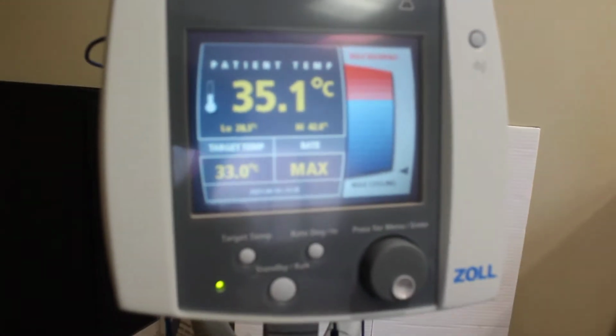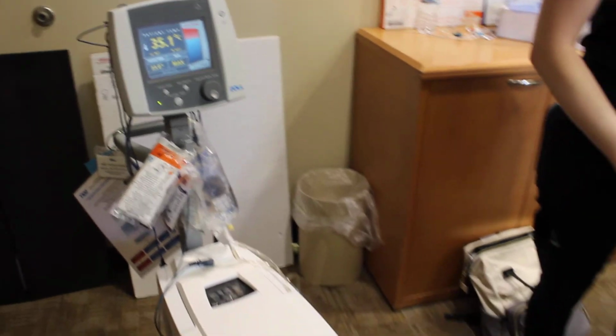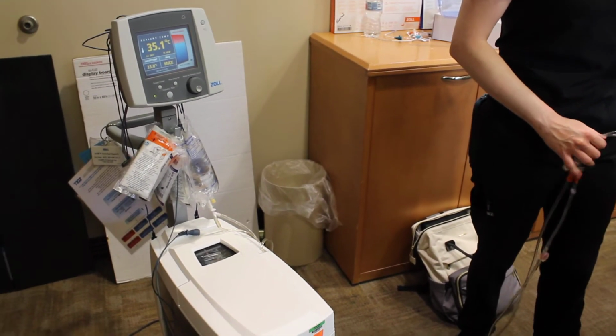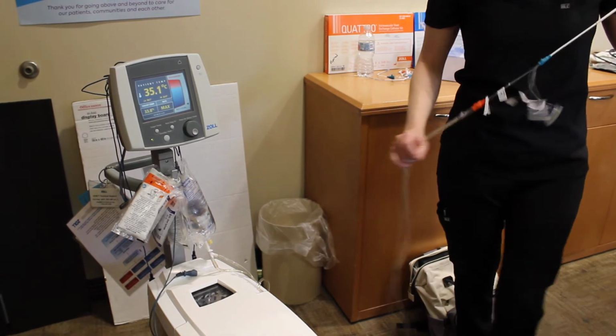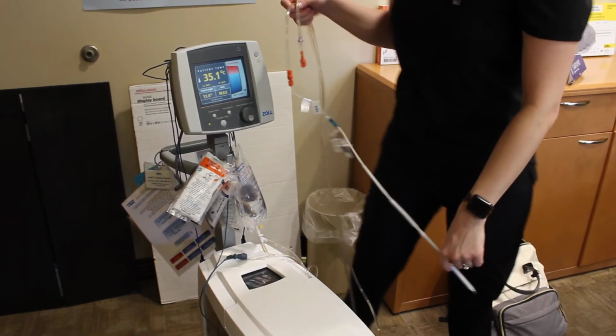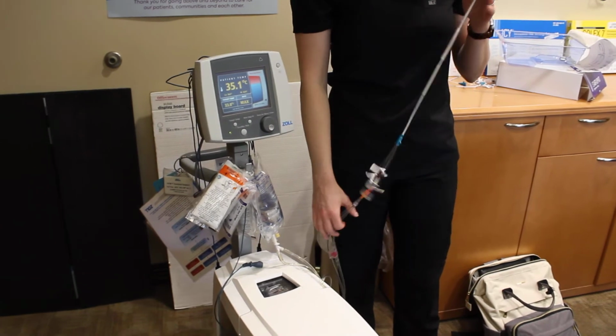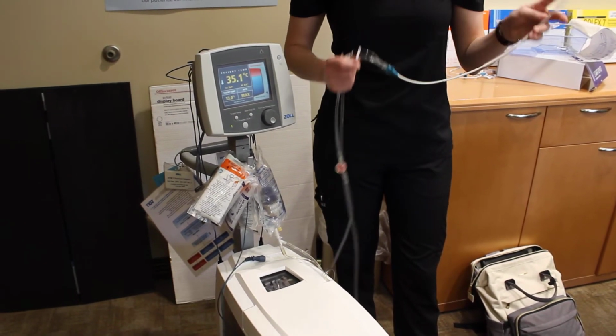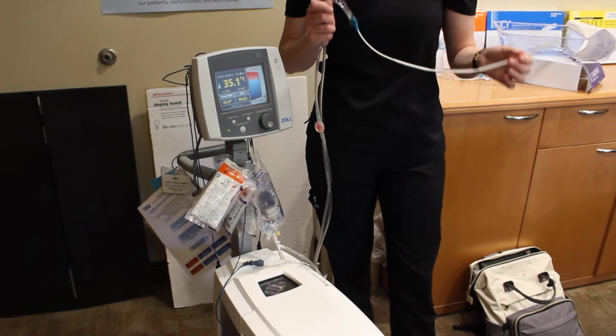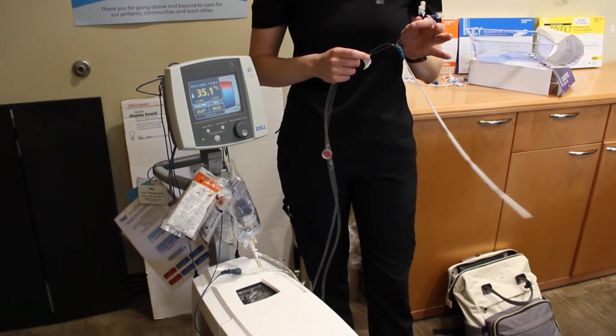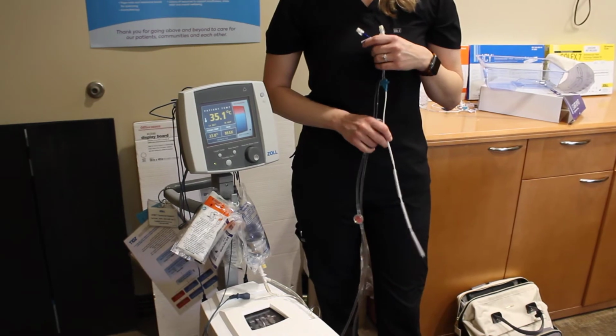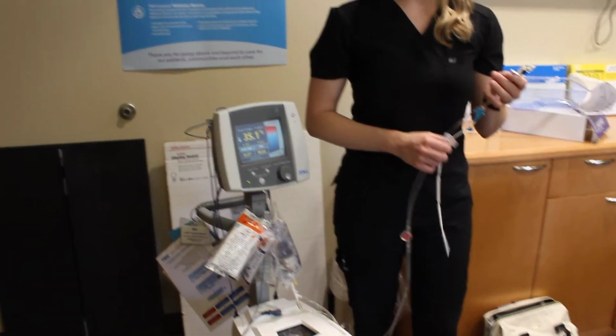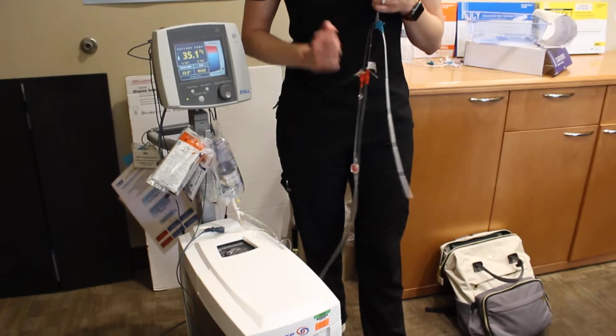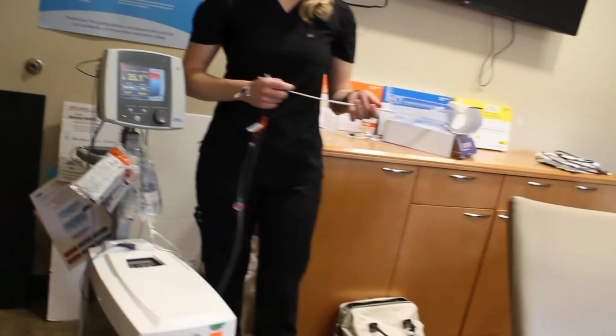So this Quattro has 4 balloons, whereas the IC that you guys use only has 3. This will cool your patient about 3 to 4 degrees an hour. So we're talking about getting to target temps in about an hour and a half to 2 hours. So it is very, very fast. If we needed to pause this and take our patient to CT, I'll show you how to do that. These are CT and MRI compatible. However, the lumens are not pressure injectable. So if they're using the pressure injectable machine to inject the contrast, they'll have to use another IV site or just manually inject it. But it's compatible to go in the machine.